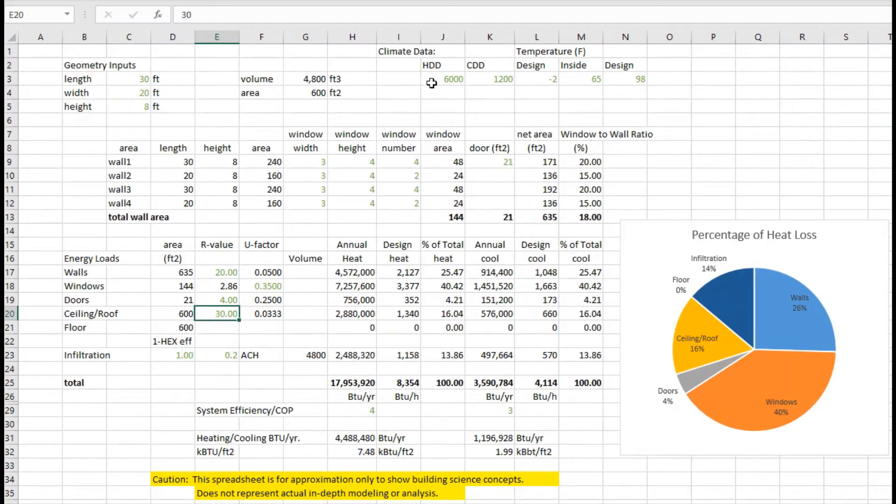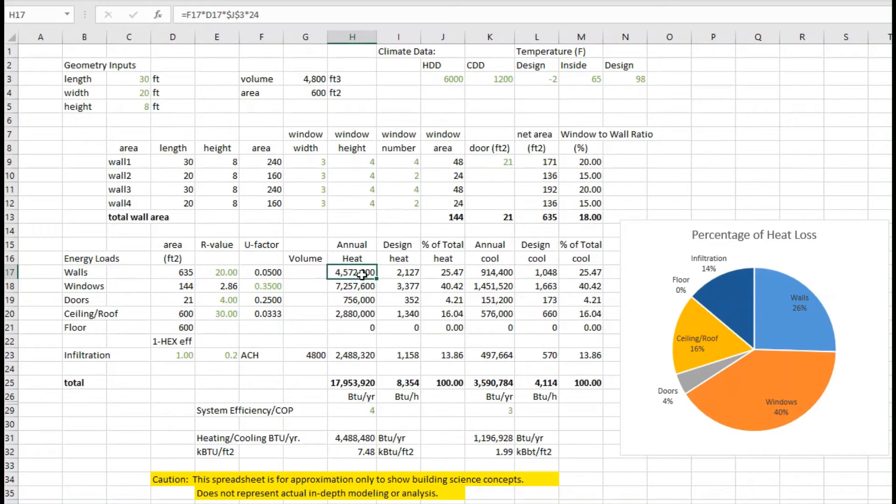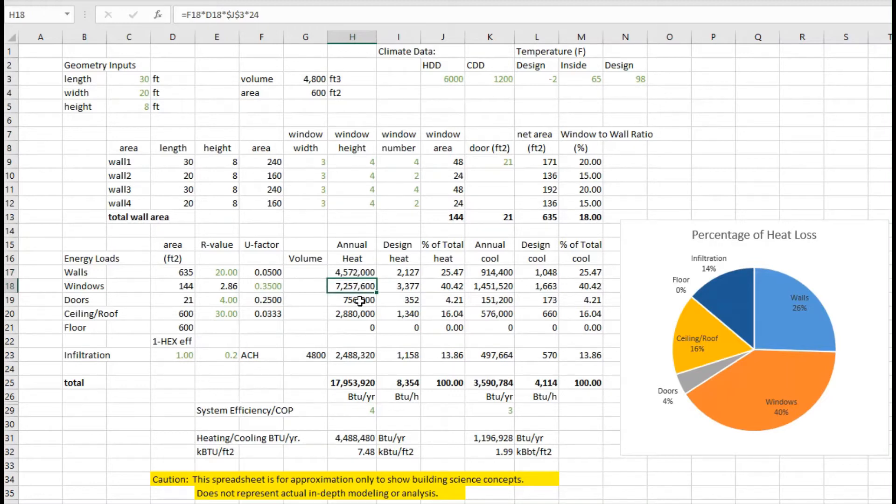From that, and using the heating degree days, we can use our approximate model that we developed in another episode to talk about what the annual heat is. So in this case, through the walls, about 4.6 million BTUs leaves the house, and we can repeat the same for the windows, the doors, the ceiling.